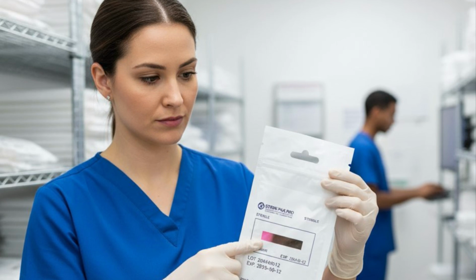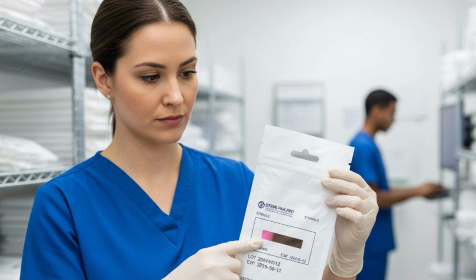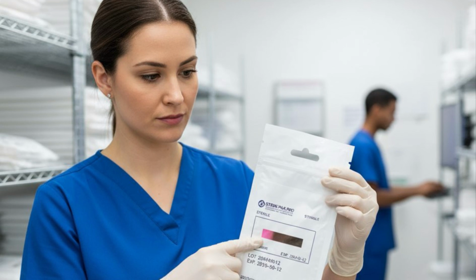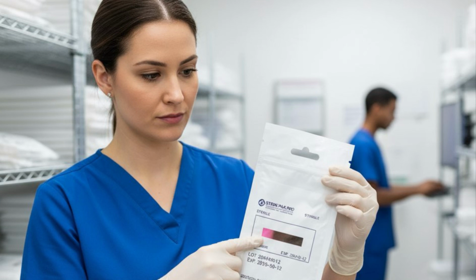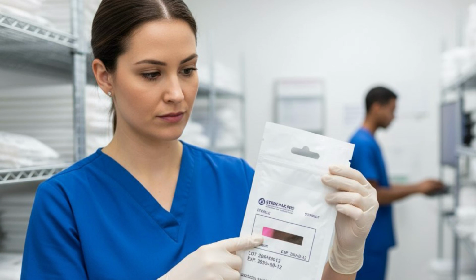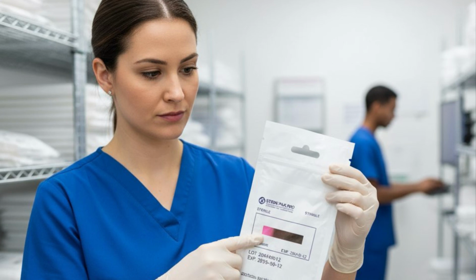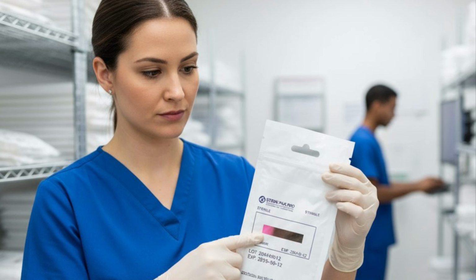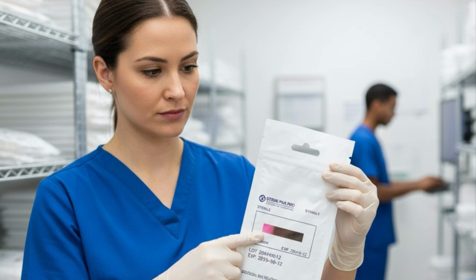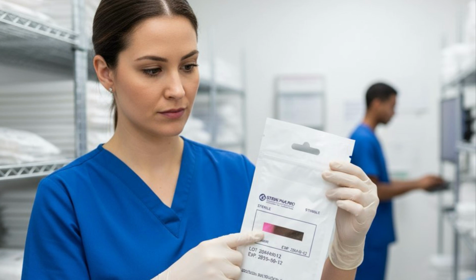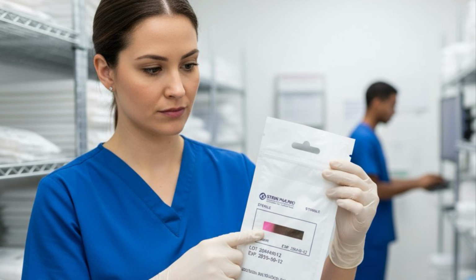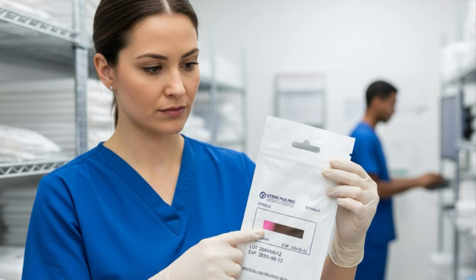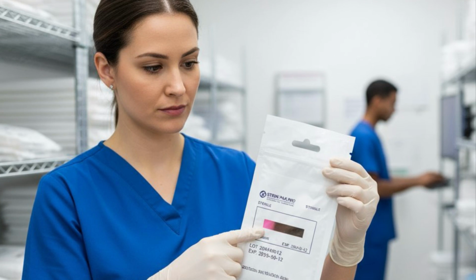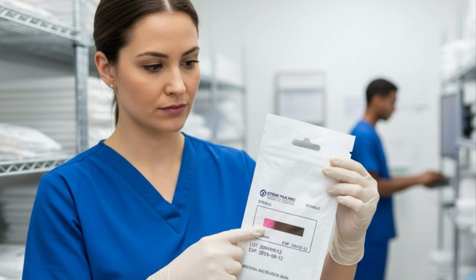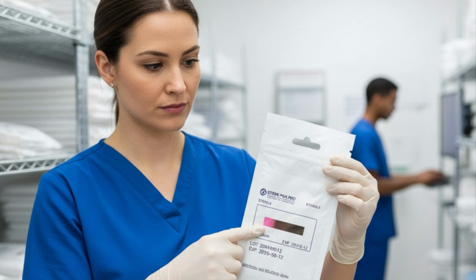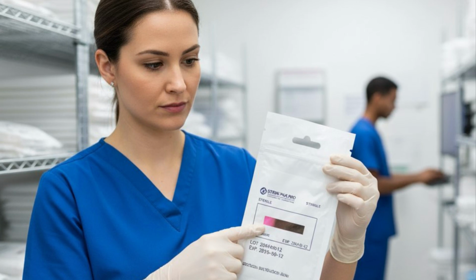Vaporized hydrogen peroxide, in other words VHP, or gas plasma, is a safer and faster alternative to ethylene oxide. It sterilizes items using a plasma field created from hydrogen peroxide vapor. This process breaks down into safe byproducts like water and oxygen, eliminating the need for a long aeration phase. Furthermore, liquid chemical sterilization is a method used for instruments that cannot withstand heat or are needed for rapid reprocessing. Peracetic acid is a common agent. While effective, this method is not as reliable as steam or gas sterilization, and items must be used immediately after processing.